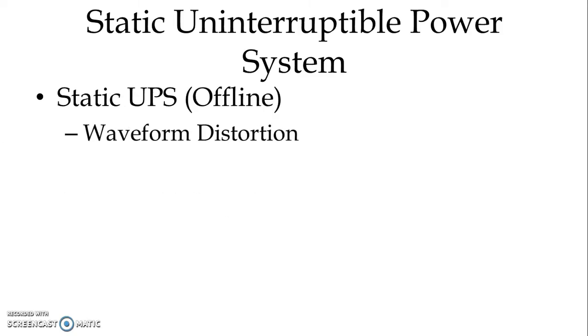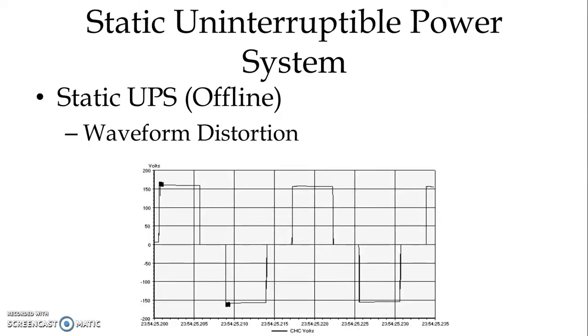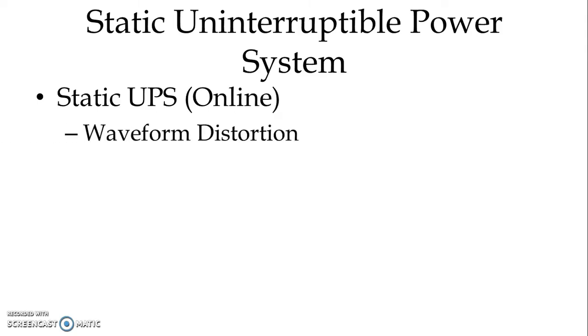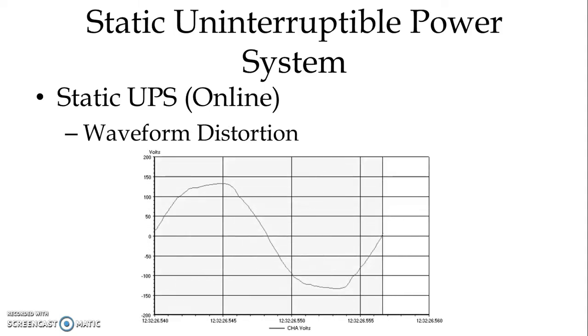In case of offline, we have waveform distortion because it is through the inverter. So we have waveform distortion like this. We have almost a square wave, and during the starting of the cycle, a ringing effect we can observe. So for this type of load where it is suitable, we can supply uninterruptible power through the static offline UPS. In case of online static UPS, again we have waveform distortion, but it is much better compared to offline static UPS. In this we also have distortion, but it is at the low order, and critical loads can be supplied with this static online UPS.